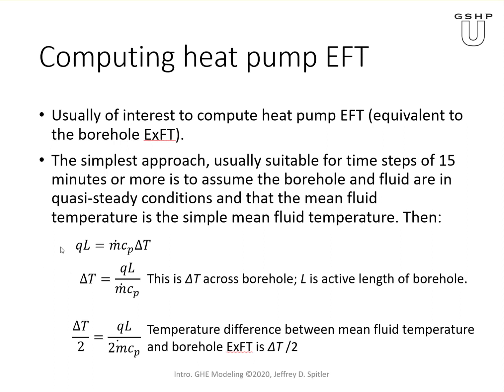From the first law of thermodynamics, the total heat transfer rate to the borehole is Q times the length of the borehole — watts per meter of borehole times the meters of borehole, or BTUs per hour per foot times the feet. That total heat input must equal the mass flow rate of the fluid times the specific heat of the fluid times the temperature change across the borehole. Note that specific heats appear in multiple places in this problem: the specific heat of the ground is rolled into the thermal diffusivity, so keep them straight from context.